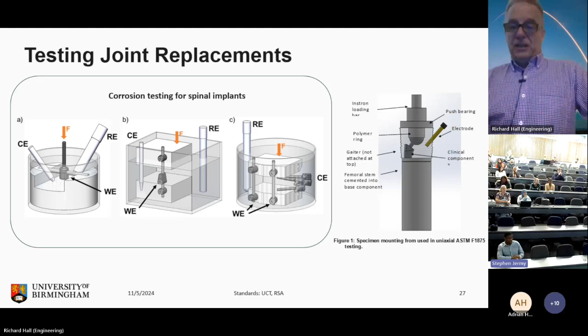The great thing about corrosion, as opposed to wear, which you would identify in the simulator test in the previous slide, is you can do this over a relatively short period of time. A few days will give you enough data to differentiate between different biomechanical or different environmental scenarios. In a simulator, a 5 million cycle test over 6 stations, so 6 joints, will take you about 4 months. And you'll get essentially 1 data point from that 4 months, which is the wear of those devices over that period of time.